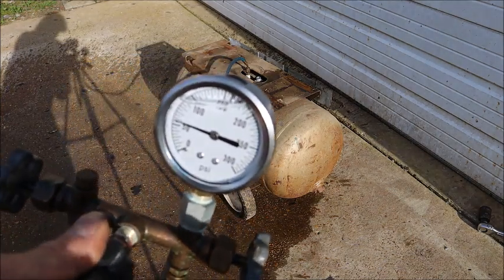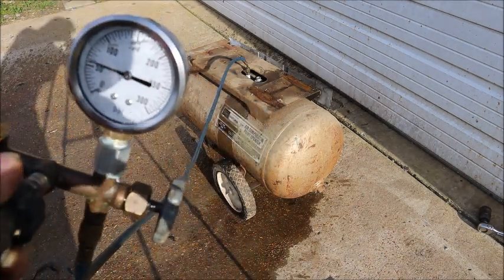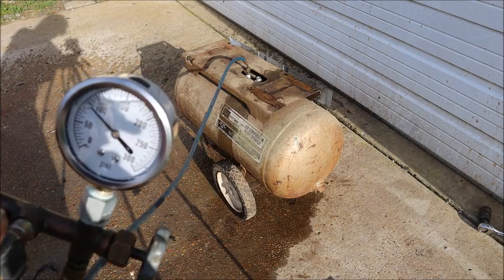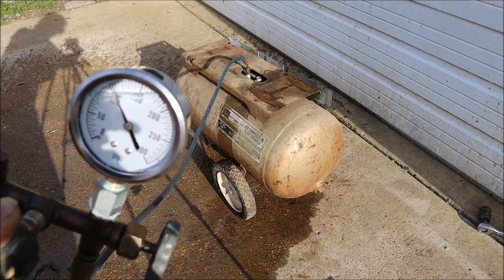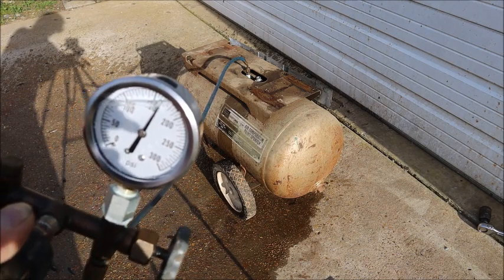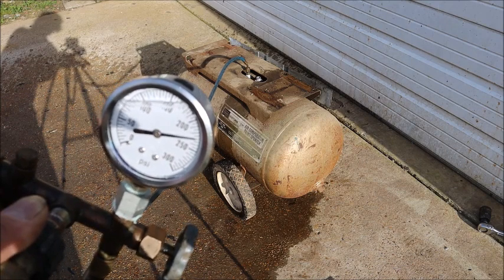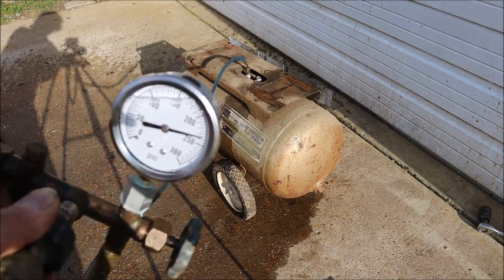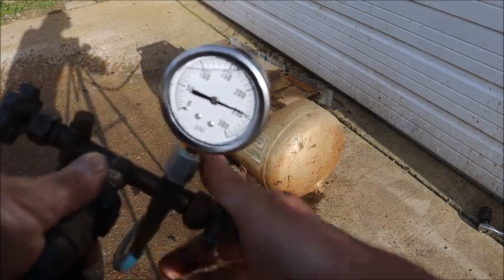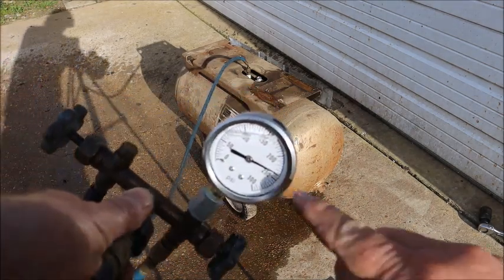The pressure pump is a positive displacement pump — it pumps a fixed flow of water, so as long as I leave that open the pressure is really low. Here we go, we're going to start building it up to 245 psi. That's rated pressure right there — and that's pretty much test pressure. I'll trap it in there. Now I've got the pump free-flowing again, but we've got the test pressure in the tank.